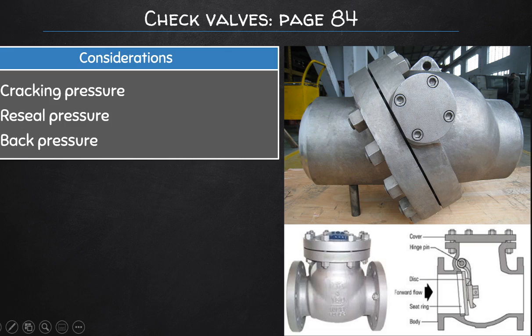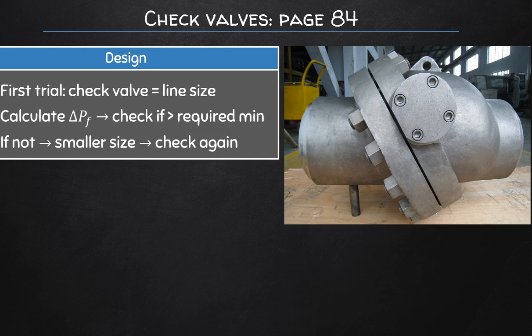to be operated under. The check valve is designed usually independently, but its pressure drop is of course included in the pressure drop calculations when you determine the frictional pressure losses. So firstly, choose the size of valve that corresponds best to the line size.